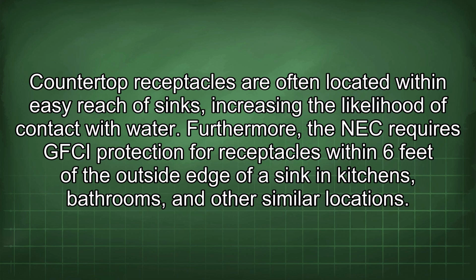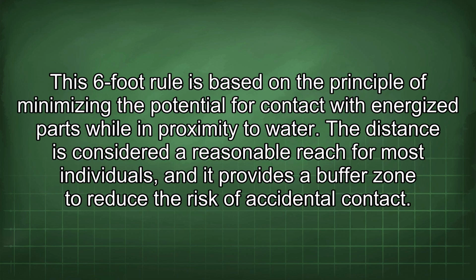Furthermore, the NEC requires GFCI protection for receptacles within 6 feet of the outside edge of a sink in kitchens, bathrooms, and other similar locations. This 6-foot rule is based on the principle of minimizing the potential for contact with energized parts while in proximity to water. The distance is considered a reasonable reach for most individuals, and it provides a buffer zone to reduce the risk of accidental contact.